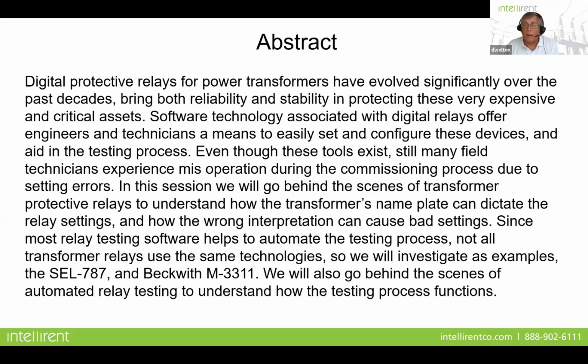So I want to focus on transformer protection, because I think this is one of the areas where most everybody gets involved if you're into relay testing, or if you're a relay engineer that does settings. We're going to give some examples of where that process can go wrong and how to find it before something bad happens, like a nuisance trip when you go to energize the relay. So we'll look at two examples. Not all digital relays are the same in terms of how they're set or how they look. They can vary quite a bit, even though they're both doing the same job of protecting our transformer. So we're going to go behind the scenes a little bit and take a look at the setting and the commissioning process.